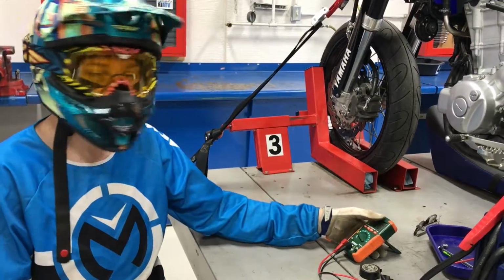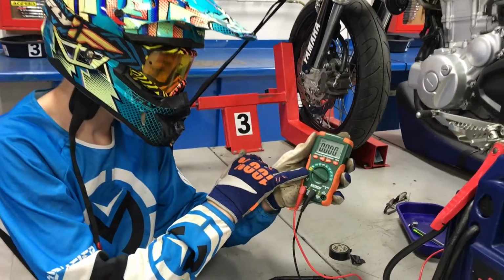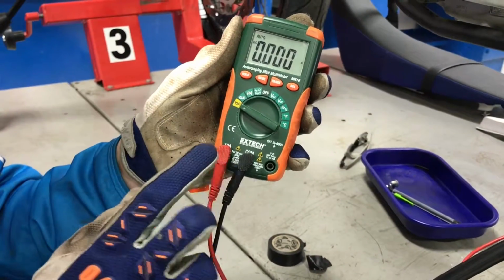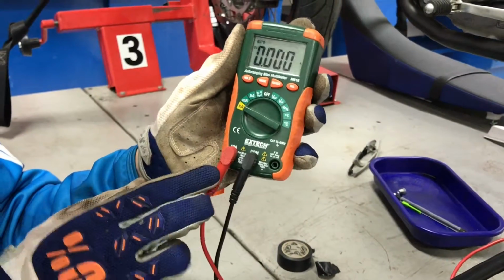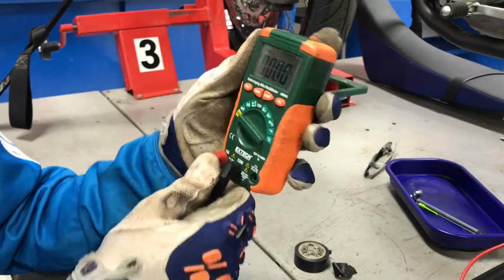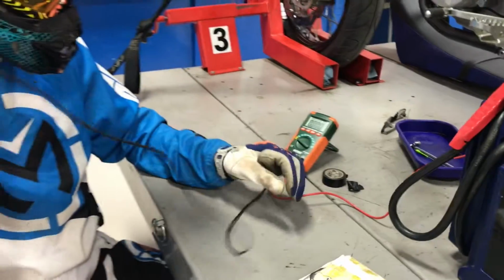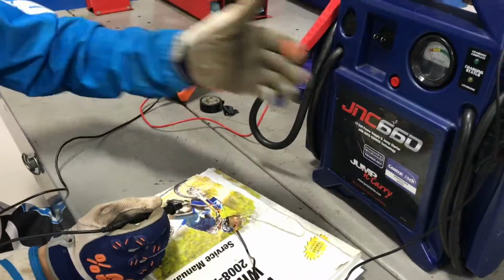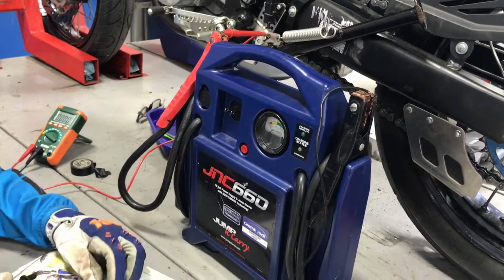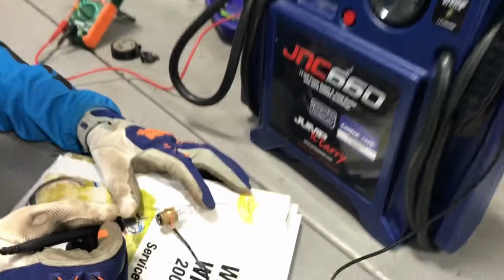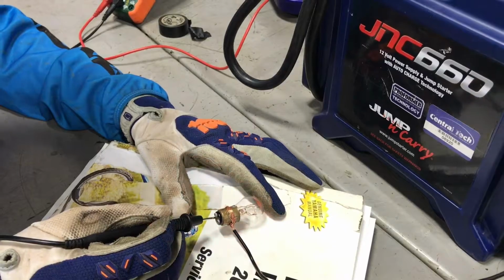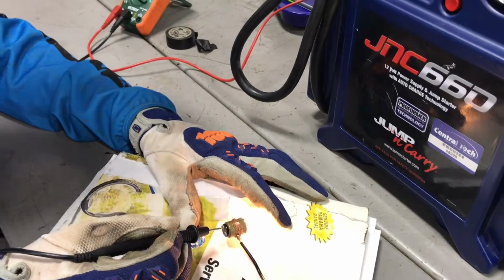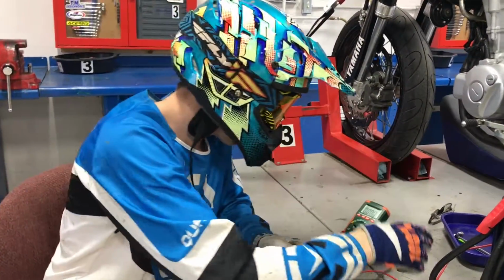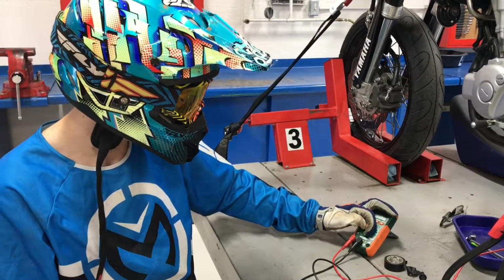Alright, we're moving on to amperage. First off, we would set our meter at our correct amperage setting. We also need to make sure our leads are in the correct spot to measure amperage, as you can see. So in this case, what we did is we just got a jumper box and we ran wires to the ground part of our light bulb, and then we just ran a hot, and let's see what we get. Got 0.46 amps, and that is how you would check amperage with a multimeter.